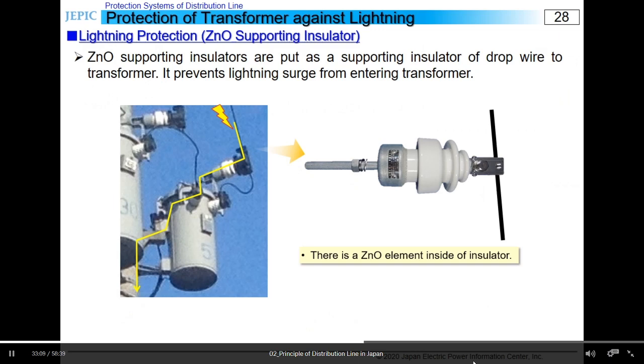This is a ZNO supporting insulator. This equipment is installed as a supporting insulator which holds the drop wire from the high voltage line to the transformer. As in its name, it has a zinc oxide element in it and prevents lightning surge from invading into a transformer.